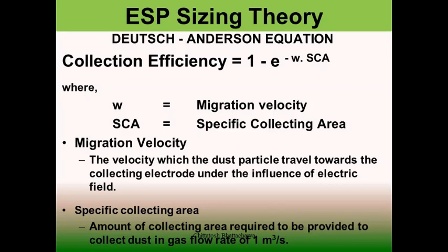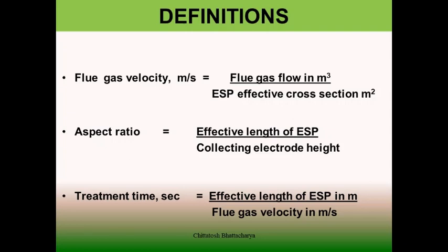ESP sizing is dependent on the Deutsch-Anderson equation, which expresses collection efficiency as: η = 1 − e^(−W × SCA), where W is the migration velocity and SCA is the specific collecting area. Migration velocity is the velocity at which dust particles travel towards the collecting electrodes under the influence of the electric field. Specific collecting area is the amount of collecting area required to collect dust from a gas flow rate of 1 cubic meter per second. Flue gas velocity is measured in meters per second — it is the flue gas flow in cubic meters divided by the ESP effective cross-sectional area in square meters.